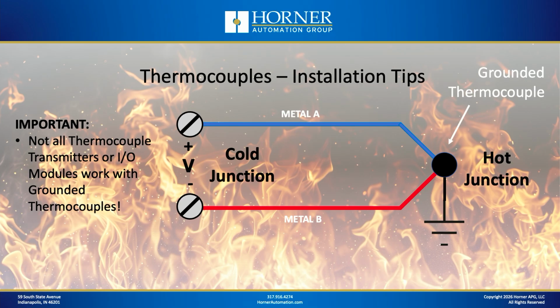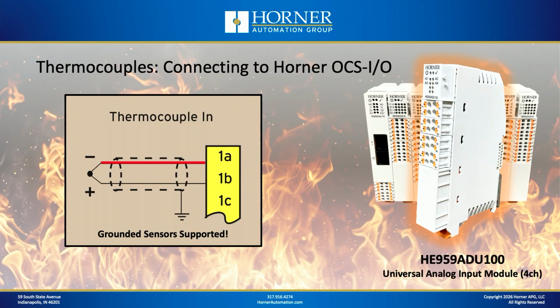But not all measuring instruments can handle grounded thermocouples. So make sure that if a grounded thermocouple is what you need, because you need super fast response, for instance, that you use an instrument that can handle that. Or, if the response time isn't super critical, then before you purchase your thermocouple probe, make sure that you check out your measuring instrument to see what types of thermocouples it can support. Can it support grounded thermocouples or not?